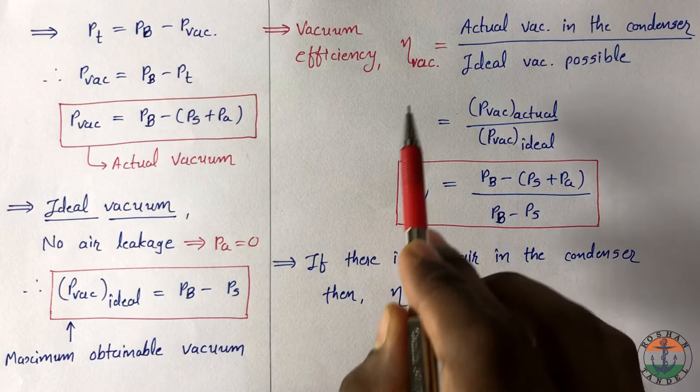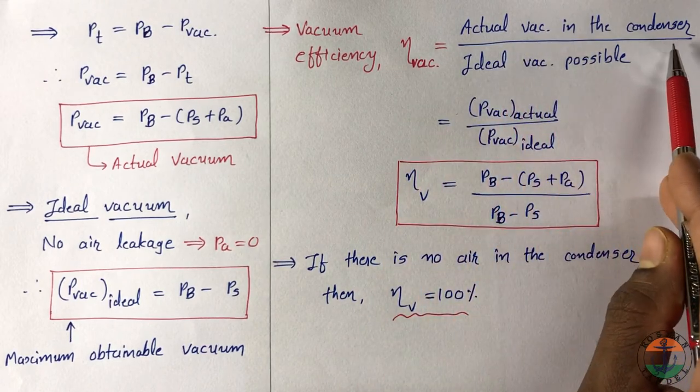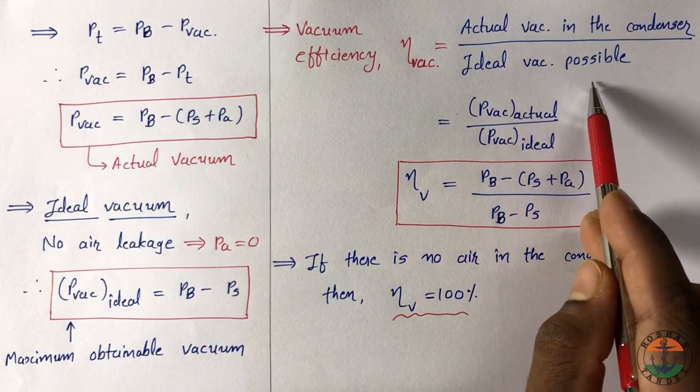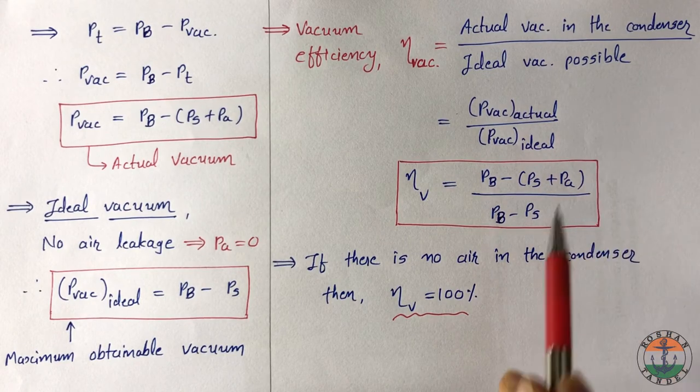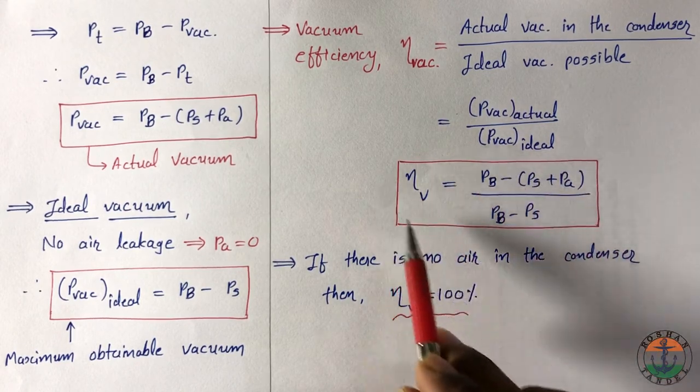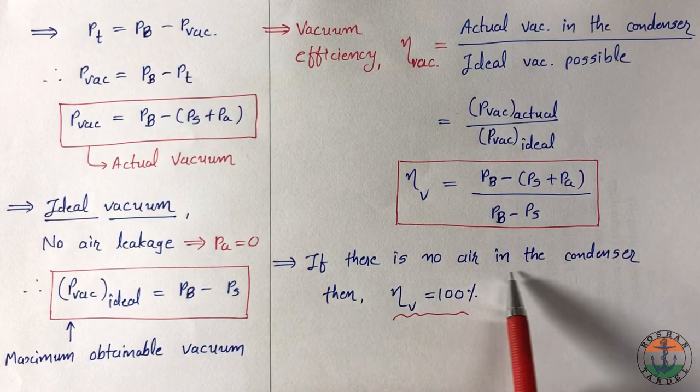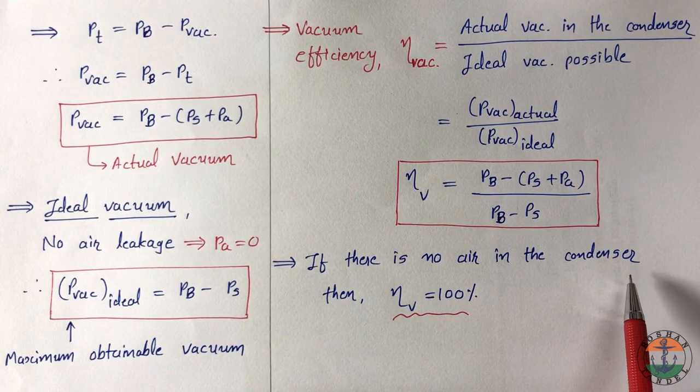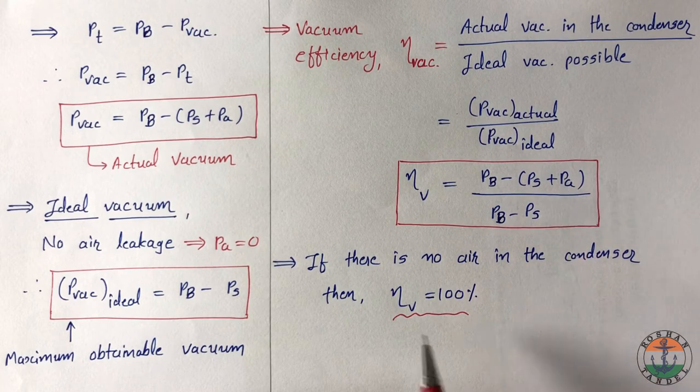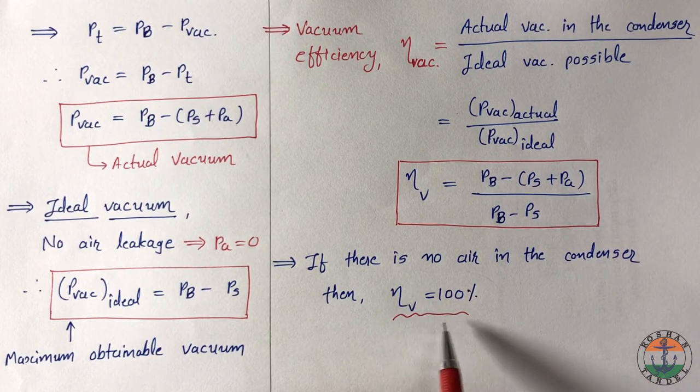Vacuum efficiency is defined as actual vacuum in the condenser divided by ideal vacuum possible. So we will get this equation. If there is no air in the condenser, then Pa equal to 0 and vacuum efficiency will be 100%.